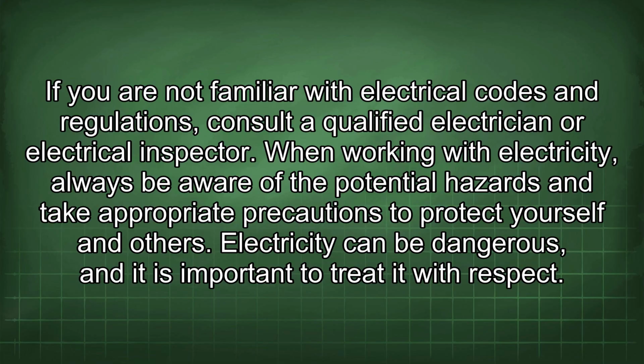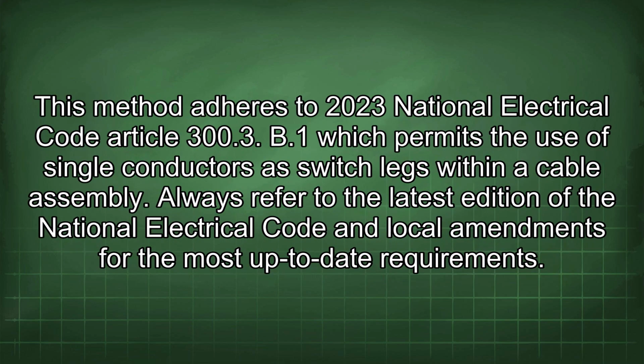When working with electricity, always be aware of the potential hazards and take appropriate precautions to protect yourself and others. Electricity can be dangerous, and it is important to treat it with respect. This method adheres to 2023 National Electrical Code Article 300.3(B)(1), which permits the use of single conductors as switch legs within a cable assembly. Always refer to the latest edition of the National Electrical Code and local amendments for the most up-to-date requirements.